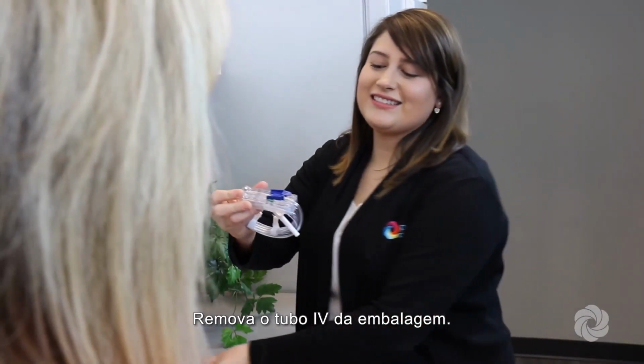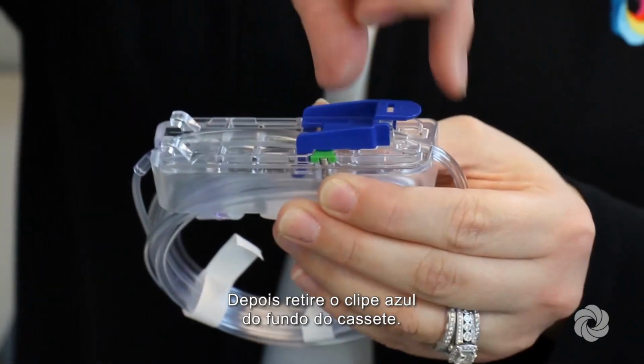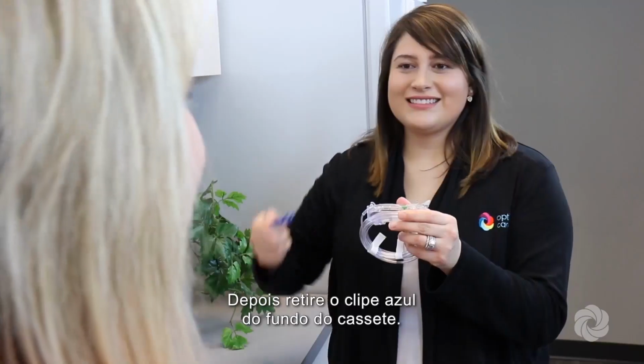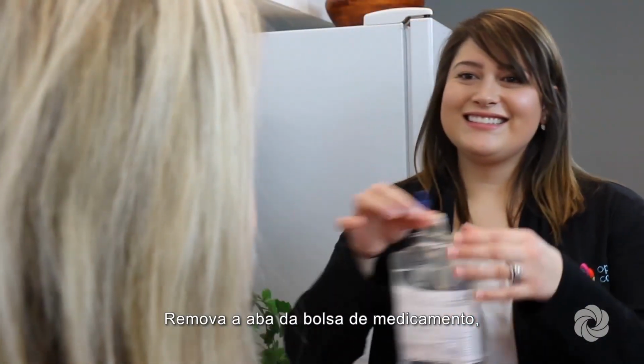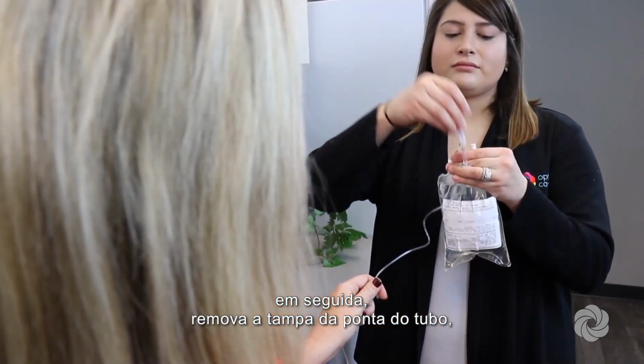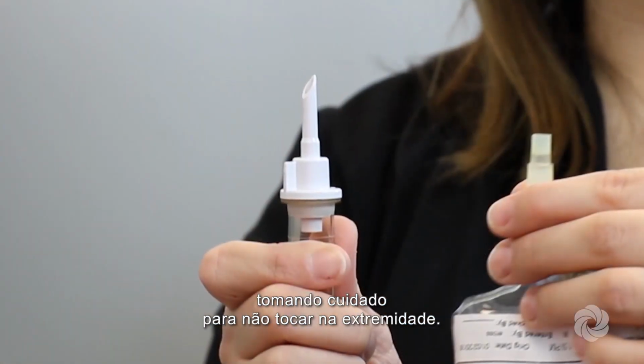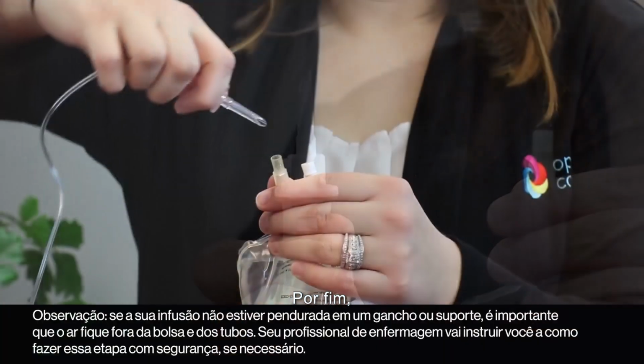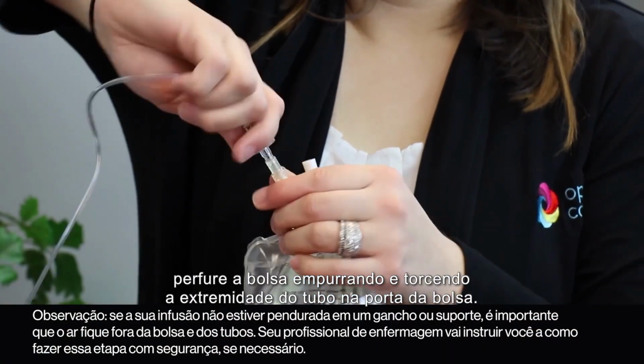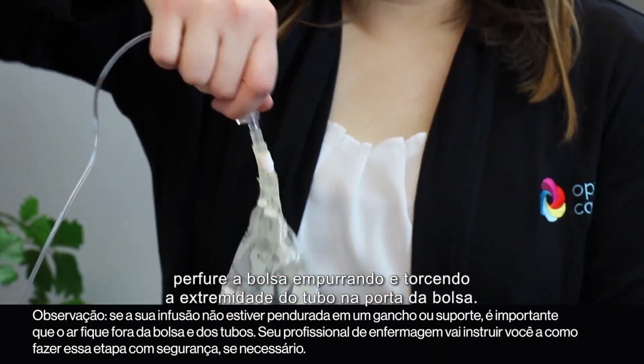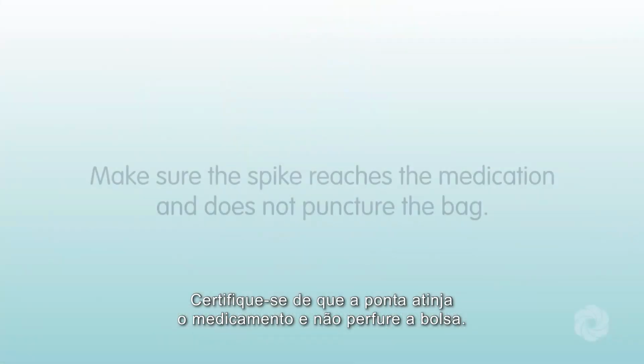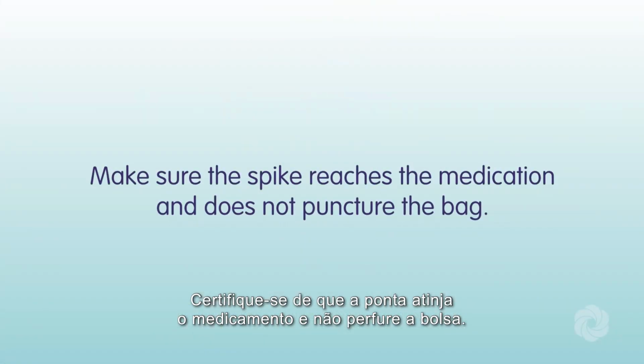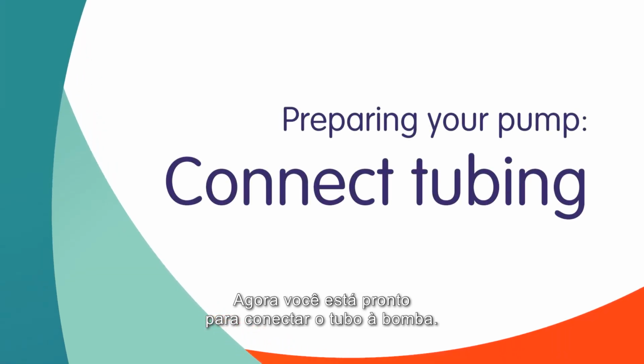Remove the IV tubing from its package, then remove the blue clip from the bottom of the cassette. Remove the tab from the medication bag. Then remove the cover from the spike of the tubing, being careful not to touch the end. Lastly, spike the bag by pushing and twisting the end of the tubing into the bag port. Make sure the spike reaches the medication and does not puncture the bag. You are now ready to connect the tubing to the pump.